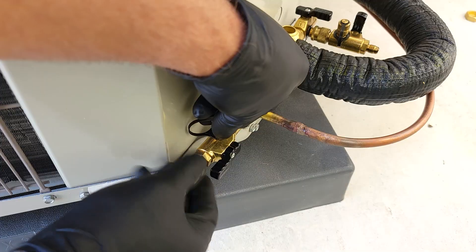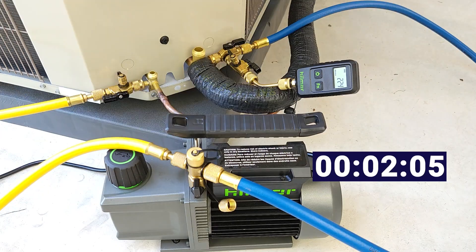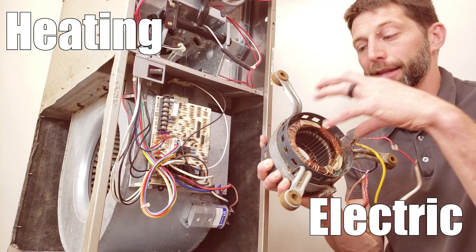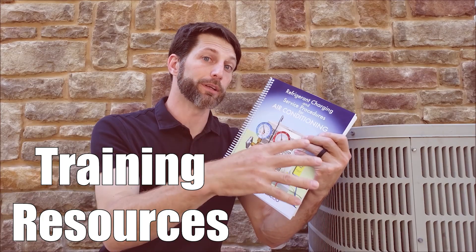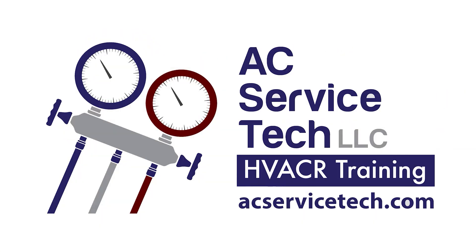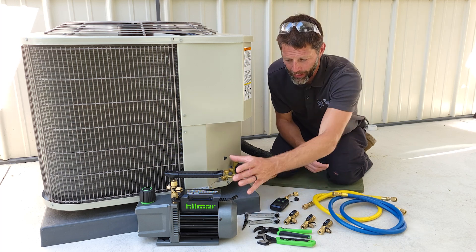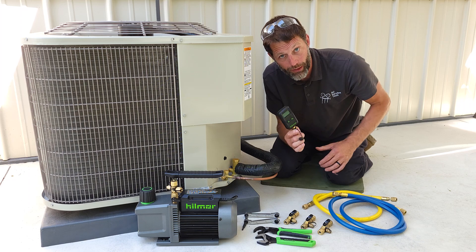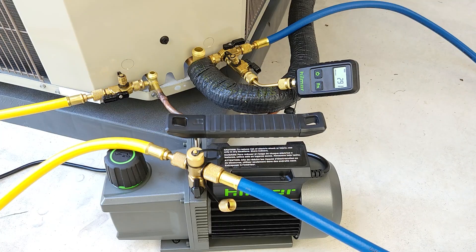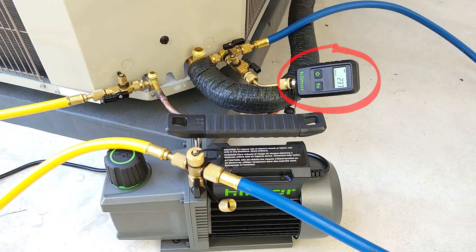In this HVACR training video, we're going over how to pull a vacuum on an air conditioning system step-by-step in order to allow refrigerant into the tubing. We're going to be pulling a vacuum without a manifold gauge set, using only two hoses and our 5 CFM vacuum pump from Hilmor. We're also using a digital vacuum gauge so we'll be able to see incremental changes as we remove air, nitrogen, and water vapor out of the system.